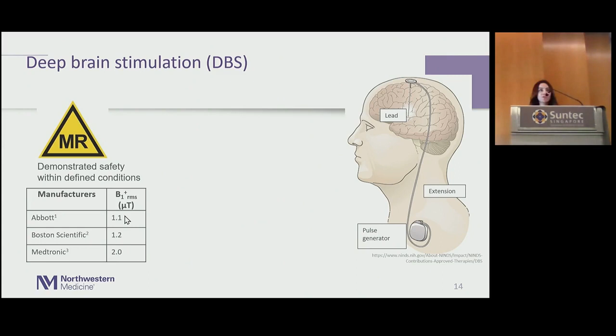Now, there are MR conditional DBS systems for horizontal scanners. It's not that they don't exist. The problem is when you look at the conditions, they tell you that you have a limit on the maximum B1 plus RMS. For example, the Abbott system, which is the one that's implanted in our patient, doesn't allow us to go above 1.1 microtesla. This is what I got from my technologist in our Memorial Hospital. All of the scans that we want to do have B1 plus much more than what the manufacturer allows us to do. So they are MR conditional on paper, but the conditions are so stringent that practically we can't scan them. That's the problem.